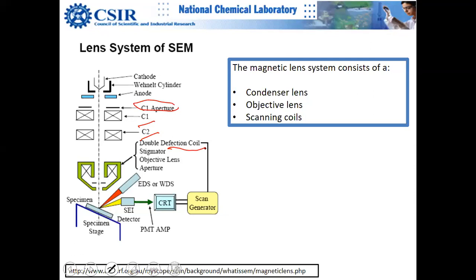You have double deflection coils. The stigmator is a very important element — astigmatism correction is one of the most important things learned during hands-on training on SEMs. You learn how to fix the astigmatism and all related correction procedures.